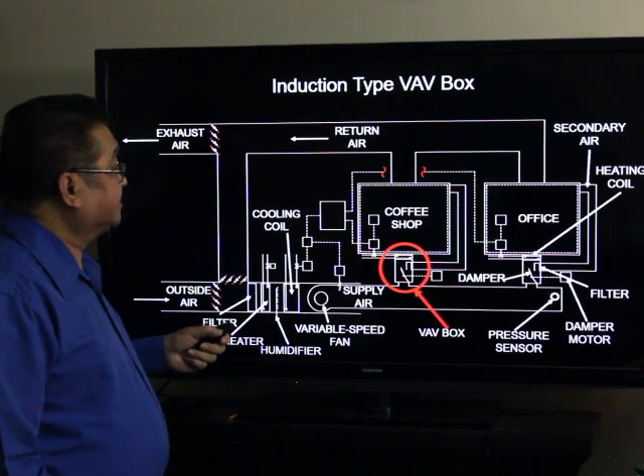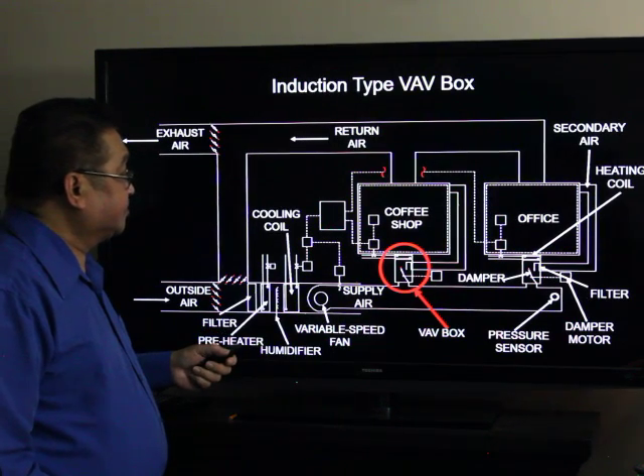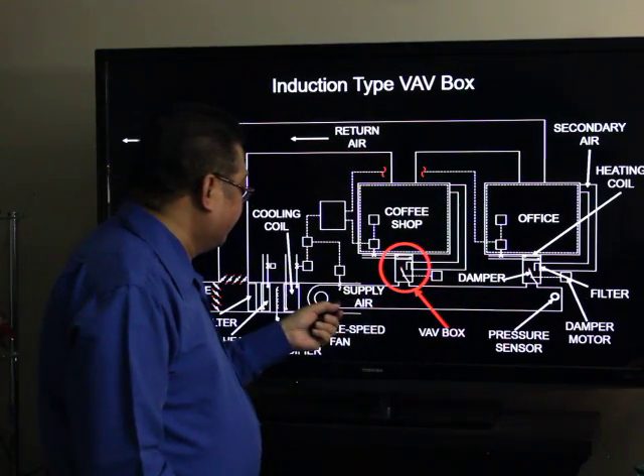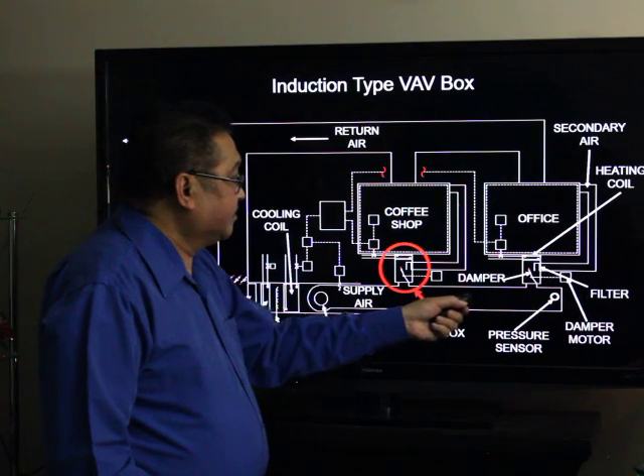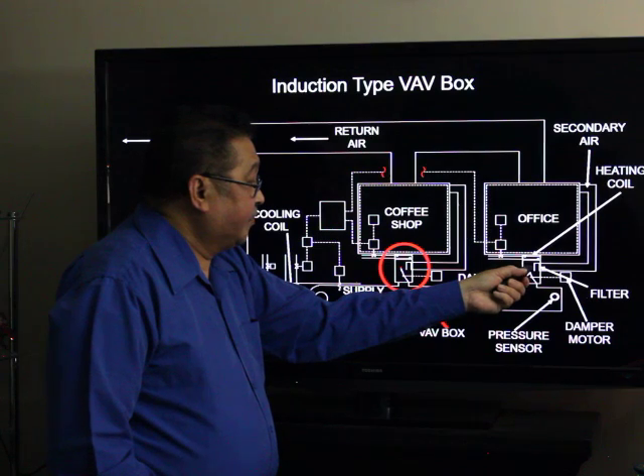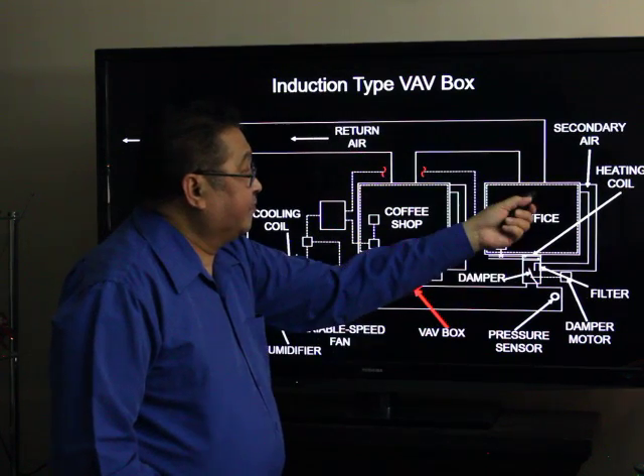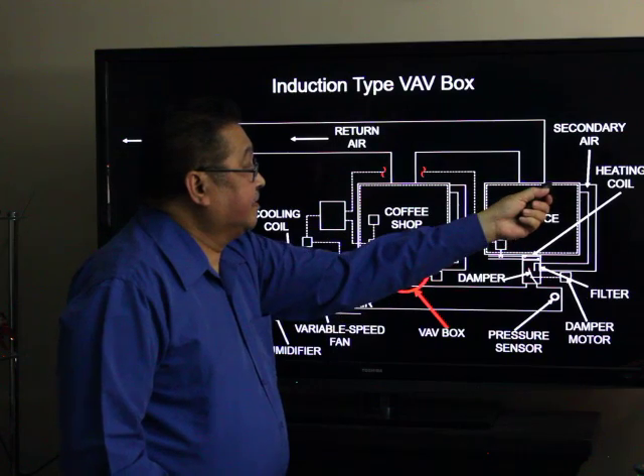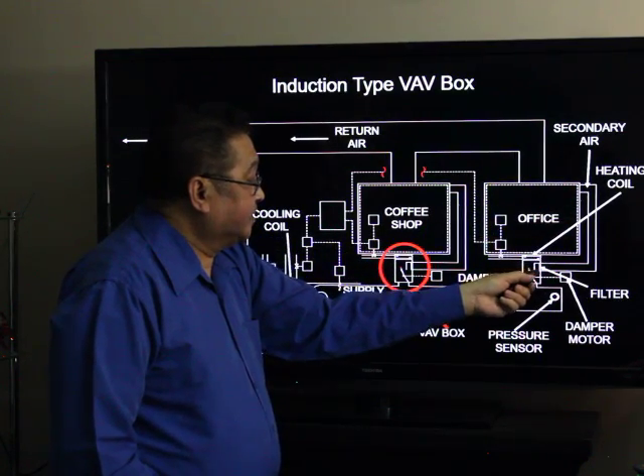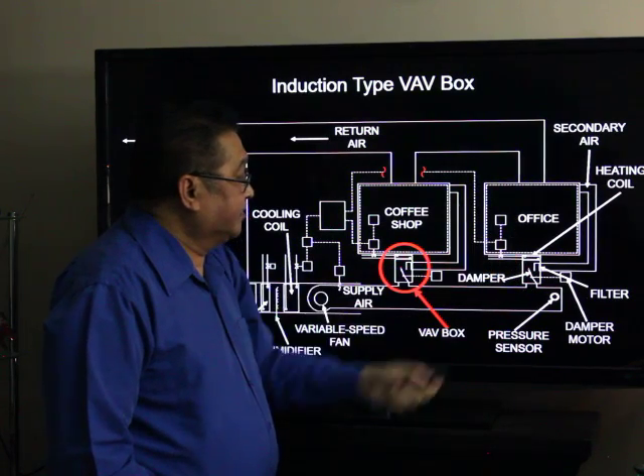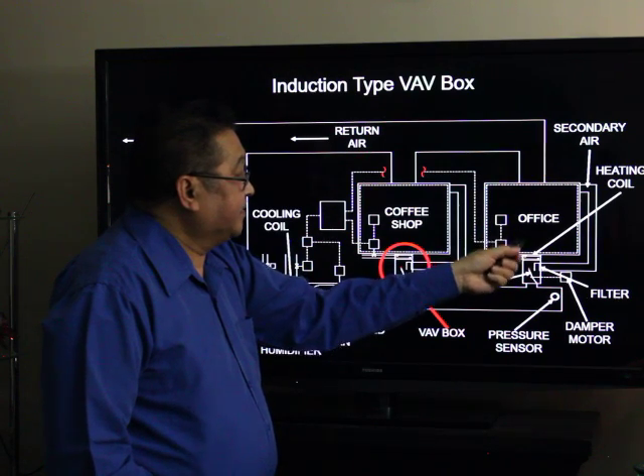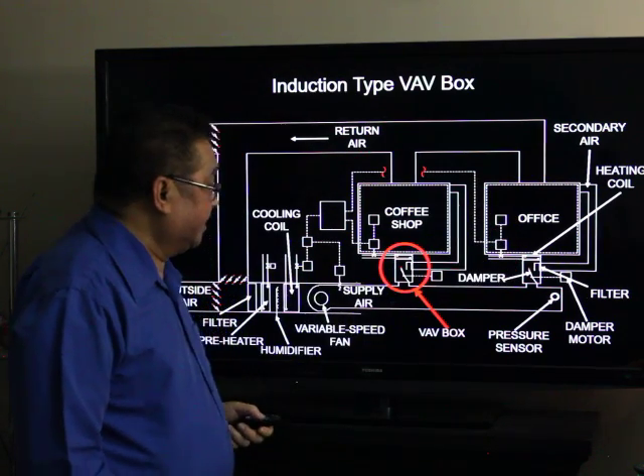To solve the cold air dumping problem, we have the induction type VAV box. A damper controls the amount of cool air going to the zone, and it provides a venturi effect where part of the zone air — secondary air — is recirculated and sucked through the venturi back into the zone, ensuring a constant flow of air to avoid cold air dumping.